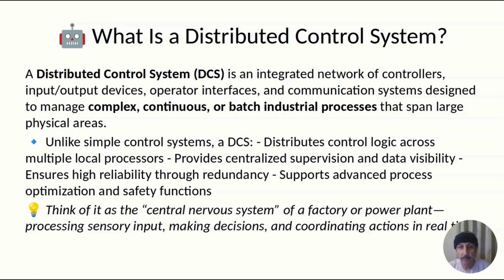Unlike a single controller managing everything, a DCS spreads intelligence across the plant. Each local controller handles a specific area, for example, a distillation column or a boiler, while staying connected to a central supervisory layer. This design gives us fault tolerance, scalability, and real-time responsiveness. Think of it like a city's emergency response. Instead of having one fire station handling all of the calls, you have multiple stations, each covering a district, but all coordinated by a central dispatch. That is the DCS philosophy.